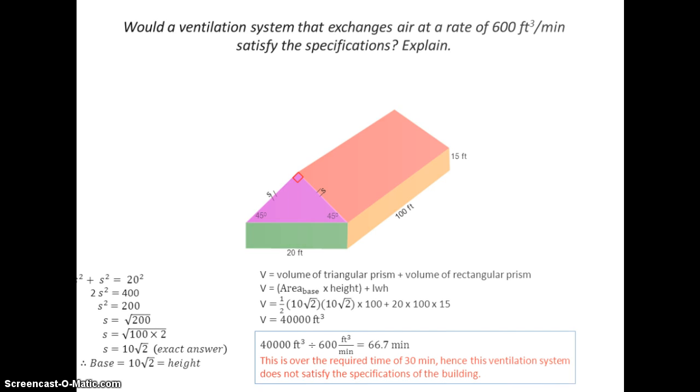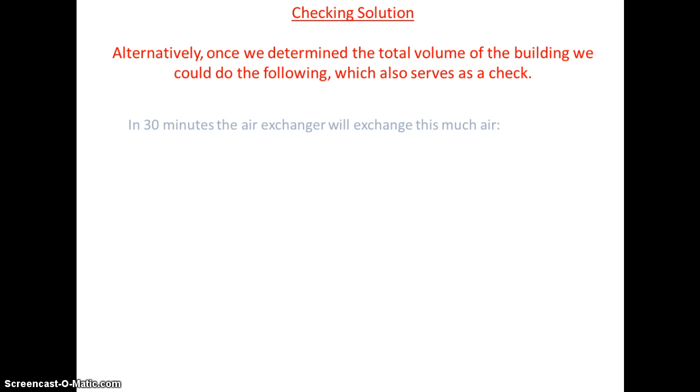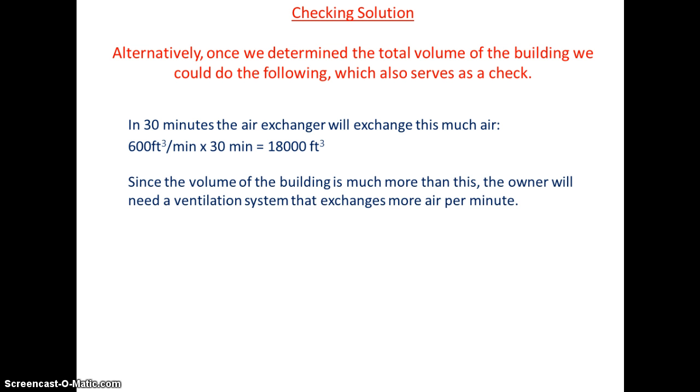To check, I could have done my solution a little differently. I could have just determined how much air is being exchanged in 30 minutes with this air exchanger. You can see 18,000 cubic feet is not anywhere near the volume of the building. Therefore, it's not an adequate system.